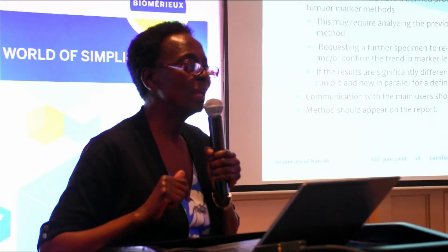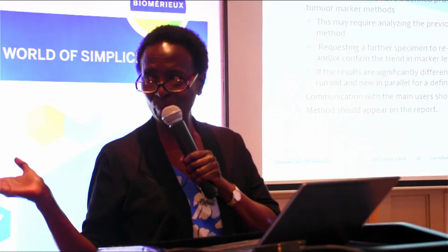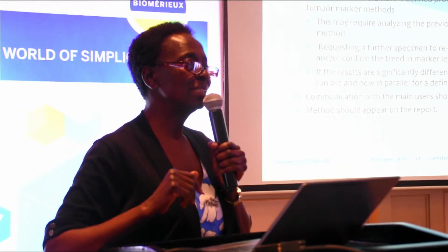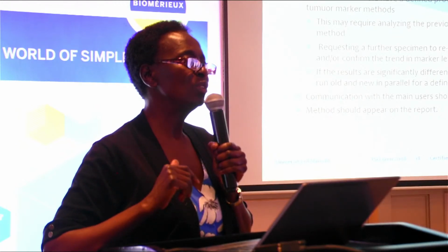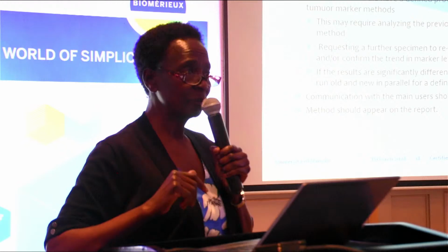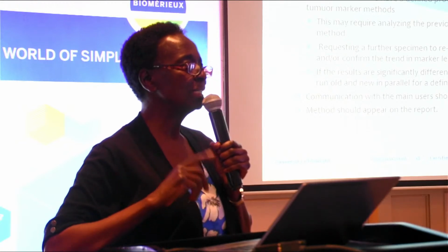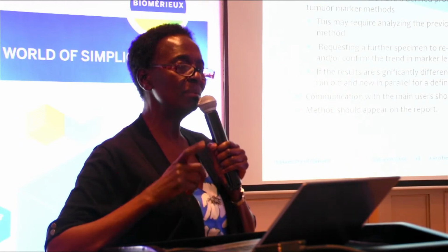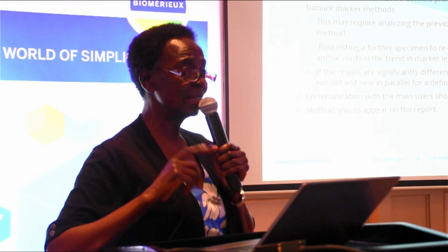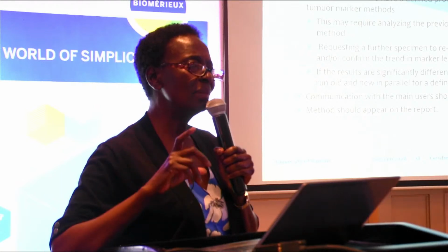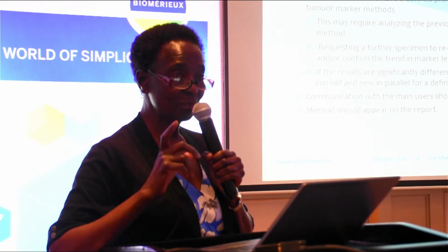Now there is a new platform being launched. Some of us are going to obtain it, and if we are going to apply it for tumor markers, that means we are going to change the method. There is a protocol for method change because of the issue of maintaining precision. Those of us who will change the method need to apply that protocol to ensure that the patient who is being monitored, and has been monitored maybe for the last 3 years on the platform you are currently using, their management doesn't change just because you change the method.